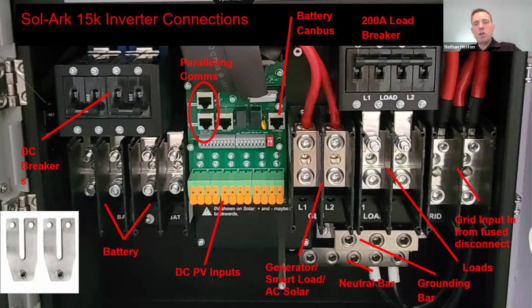That being said, if you do not have a generator, you can use the generator port as a smart load port. So I'm showing the connections here on the screen, but while we're on the topic of it, you can use the generator port as a smart load port and select to have that port automatically shut down in too high of a power demand situation. So I would recommend, if you have a very undersized system, that you would use this port for that if you are not connecting AC coupled solar or a generator.